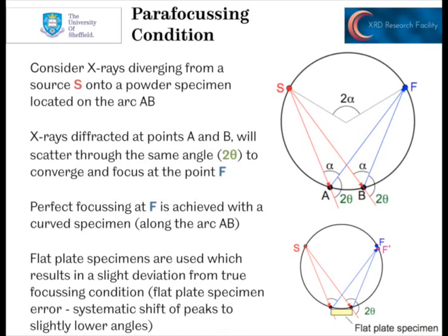The diffraction circle layout is built around a para-focusing condition. If we imagine X-rays coming from source S onto a powder specimen located on the arc AB, X-rays hitting points A and B will scatter through the same angle to converge and focus at point F. We would get perfect focusing if we have a curved specimen, so all the bits in between A and B would also focus onto point F. Obviously for most samples that would be very difficult. So in diffraction experiments we tend to use flat plate specimens, which results in a slight deviation from the true focusing condition — the outside parts of the sample are lower than the diffraction circle, so we would see peaks shifting systematically to slightly lower angles. We call this the flat plate specimen error.